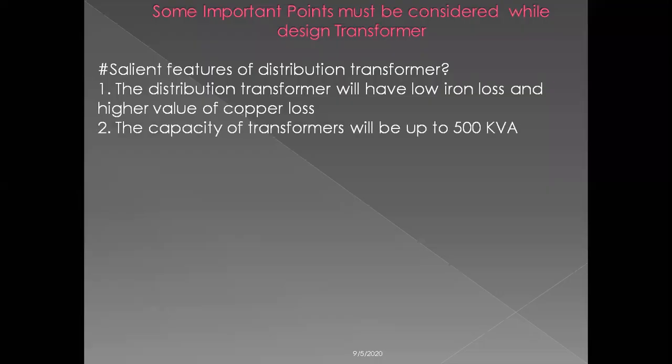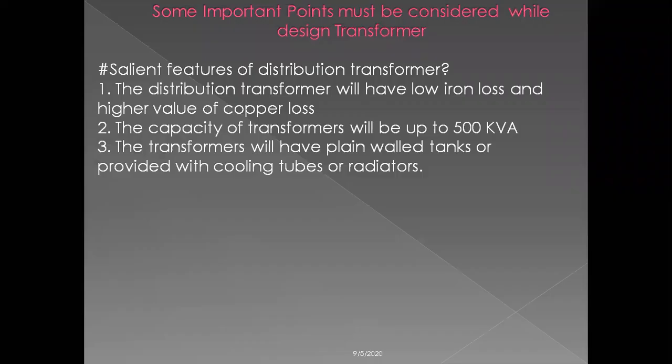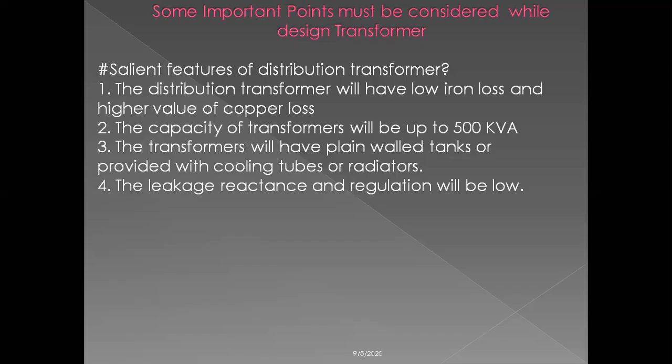Next, the capacity of distribution transformers will be up to 500 kVA. Distribution transformers will have plain walled tanks and be provided with cooling tubes or a radiator. And the fourth is that the leakage reactance and the regulation will be very, very low. So these are the four most important features that you should keep in mind while designing a distribution transformer. Now the question is, what is a distribution transformer?